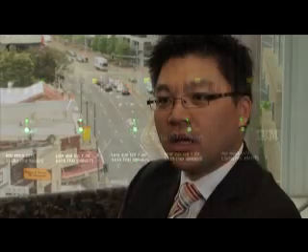There are also a lot of quick wins you can do in your data center as well. For instance, you can install blanking plates in between gaps in racks to ensure that the cold air gets to where it needs to go. You can install floor grommets in the floor to make sure that gaps in the floor tiles are sealed where it's not supposed to be. You can increase the temperature inside the room slightly by 1 or 2 degrees and increase the efficiencies of the air conditioning systems. Taking some of these simple steps will make a difference.